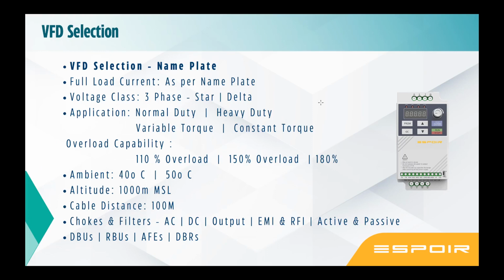So every brand has a derating factor. Derating means you reduce the size of what it is capable of delivering. For example, for 11 kilowatt, 22 amps at 45 degrees, and the derating factor is 1% per degree rise, 40 to 45 is a 5 degree rise from the design temperature, which means you need to derate by 5%.